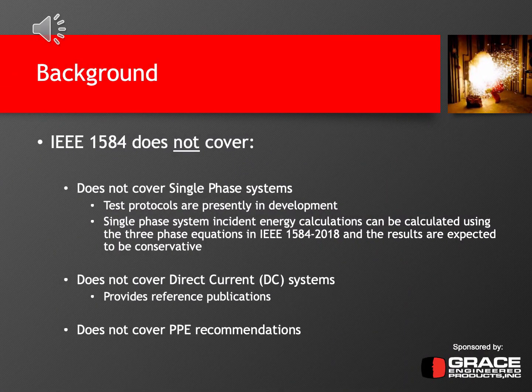So some things that IEEE 1584 does not cover is single-phase systems. Presently the standard is strictly three-phase systems. However, there are discussions and there has been some test protocols and test plans developed for single-phase systems while we're in the working group meetings. They haven't been performed yet, and they haven't actually been included in the standard. Doesn't mean that they're not going to be included in a future revision.